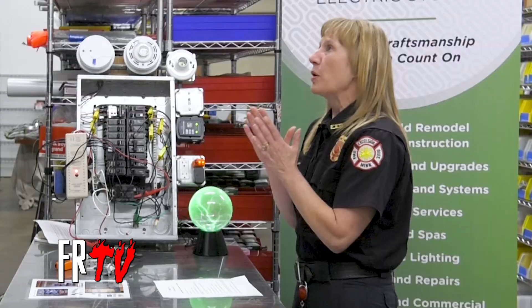So one telltale sign is you'll see what manifests as voltage drops. Let's say the furnace kicks on or the dryer kicks on and you notice your lights dim. That can be a sign of several things going on. Either that's loose connections in the electrical panel, a general overload of the electrical service itself, or a capacitor failing in the air conditioner. So there's several things that can cause that.